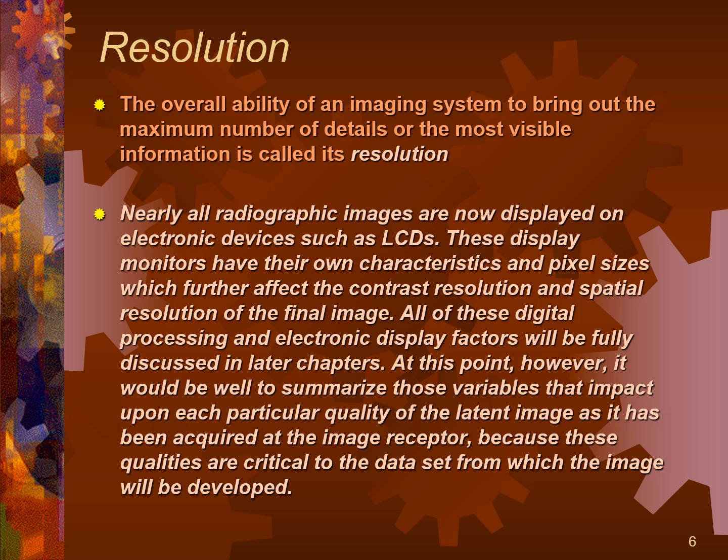Okay. The point is not every LCD monitor is the same. There's high resolution and there's low resolution monitors. How much did you invest when you bought these monitors? Native resolution, standard resolution for a hospital display workstation is usually about the equivalent of a 2K monitor, an HD monitor.